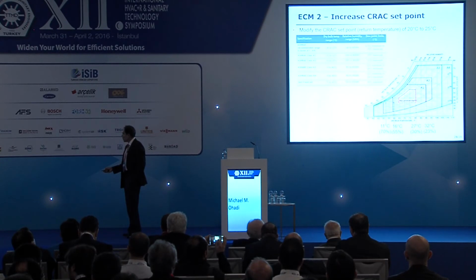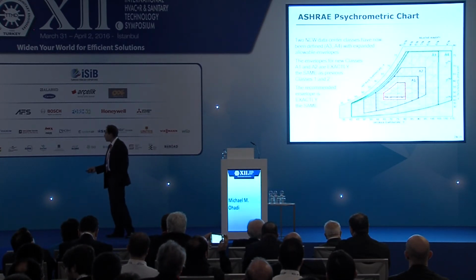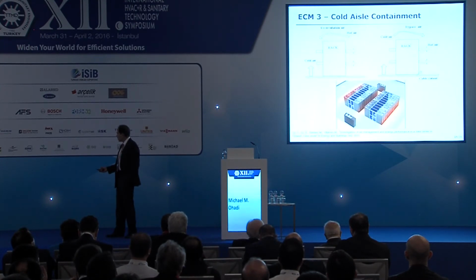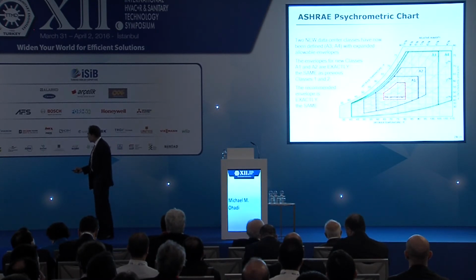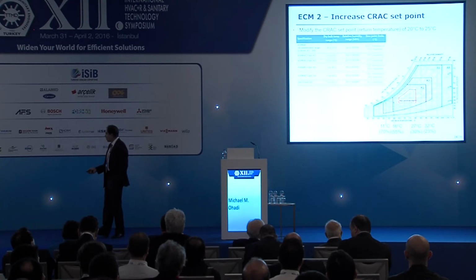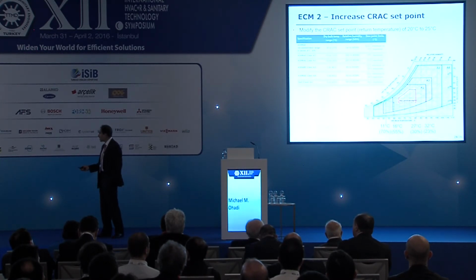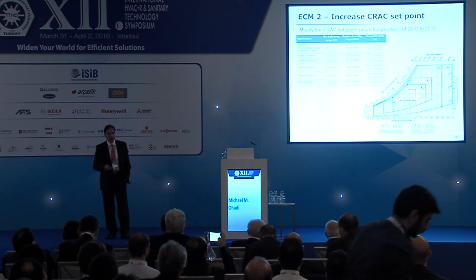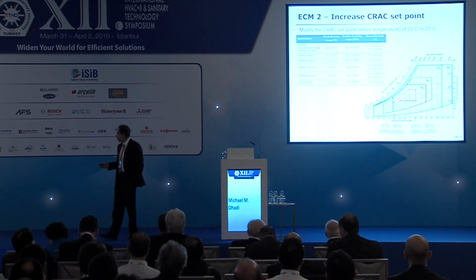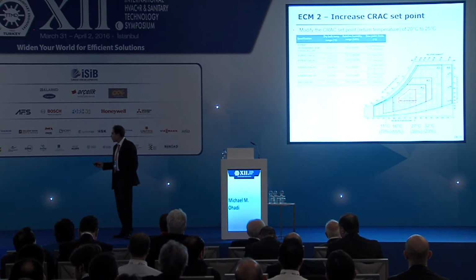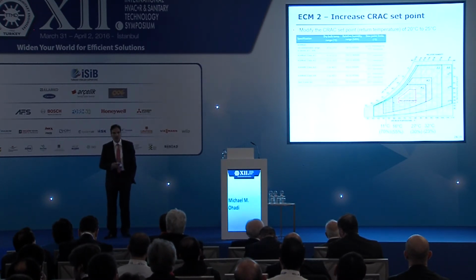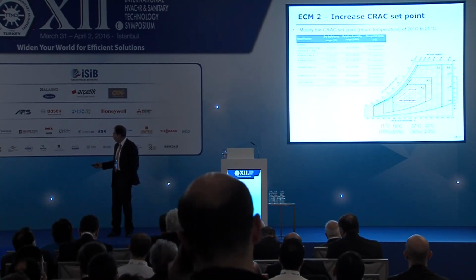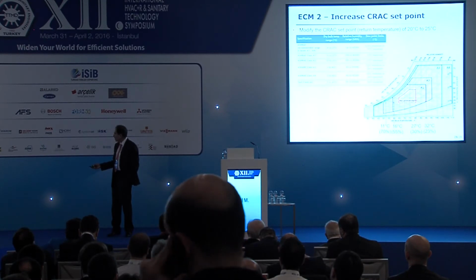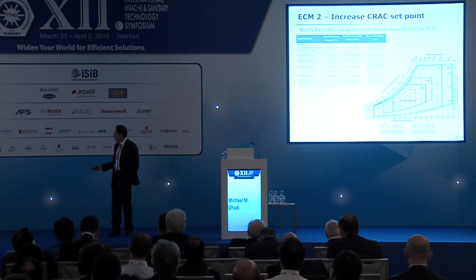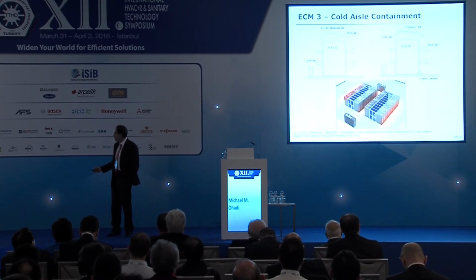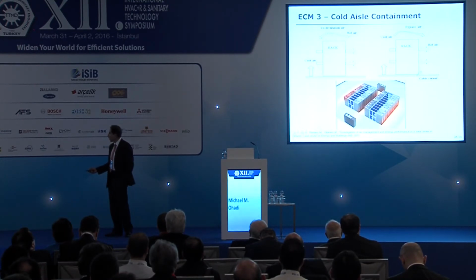So we decided to increase our set point temperatures. In this chart, we used to run at 16 degrees C—pretty cold, considering a typical computer chip can run at 80 degrees C. We set the minimum temperature at 11 degrees C and the maximum temperature to the servers at 32 degrees C. We're still being pretty conservative here, not pushing to the extremes of any of these envelopes. I'll show you in a bit what the savings from that would be.